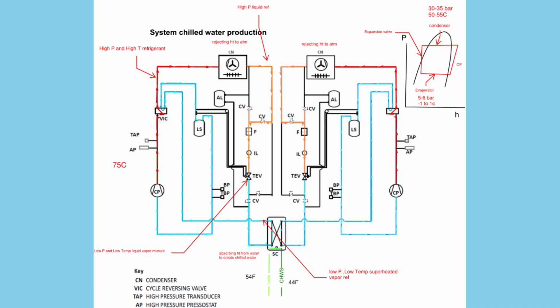1. Compression. The cycle begins as low-pressure, low-temperature refrigerant vapor enters the compressor. The compressor compresses the vapor, raising both its pressure and temperature. The refrigerant leaves as a high-pressure, high-temperature superheated vapor. 2. Heat rejection, condenser. From the compressor, refrigerant passes through the four-way reversing valve, which decides if the system is in cooling or heating mode. In cooling mode, refrigerant flows into the condenser. Here, it rejects heat to the atmosphere, air-cooled, or to condenser water, water-cooled. As heat is removed, refrigerant condenses into a high-pressure liquid.